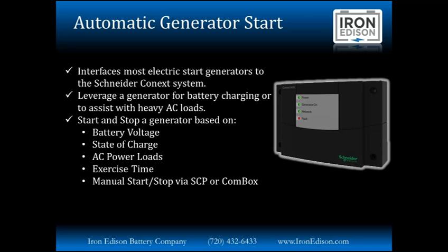The AGS, when installed, unlocks a new set of menus that allows us to start and stop the generator based on battery voltage, percent state of charge. We can start the generator to support heavy AC power loads. If the generator does not include its own exercise feature, we can use the Auto Gen Start AGS to control generator exercise. And it also allows us to manually start and stop a generator using the system control panel or the ComBox, meaning if you know you're going to start up a heavy load like a welder for the next couple hours, you can push a button on your system control panel and start the generator without having to go out to a remote room or gen building to start or stop the generator.